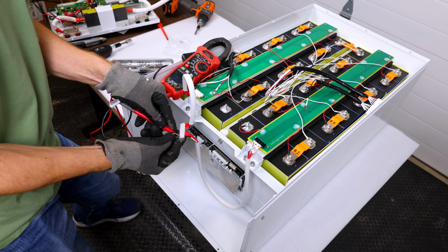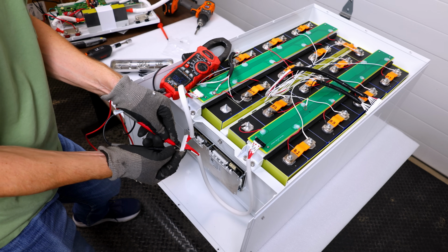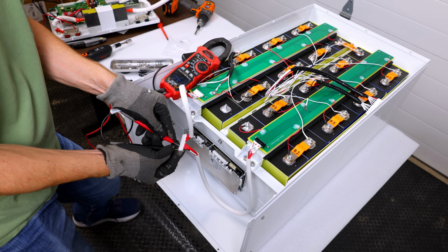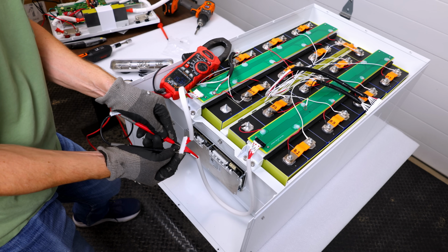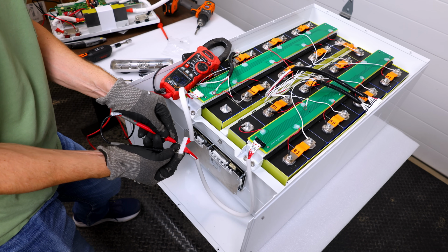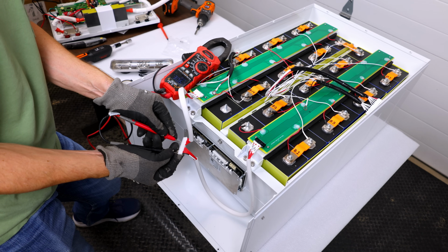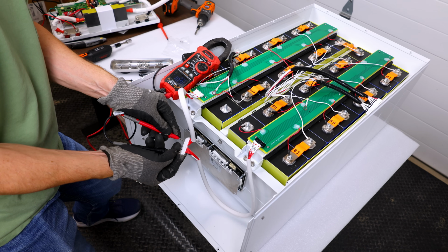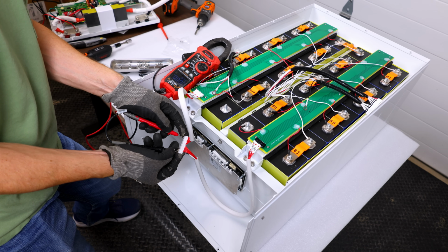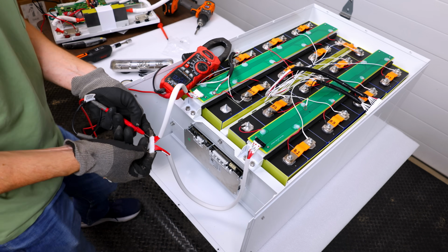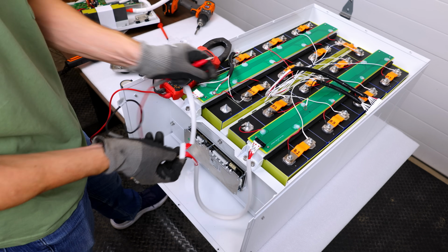Between the ground and the last one, 3.2 volts. We should work our way up: 6.5, 9, 13, 16, 19, 22, 26, 29, 32, 35, 39, 42, 45, 49. Why is that 21 millivolts? Oh, it's not connected.